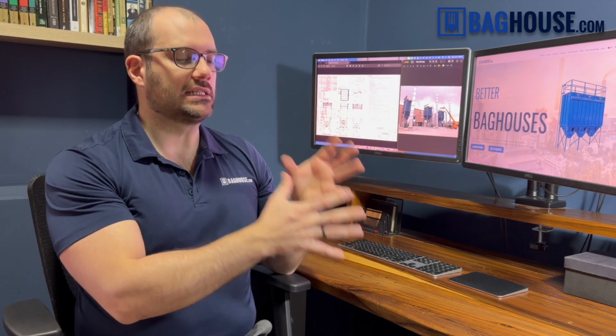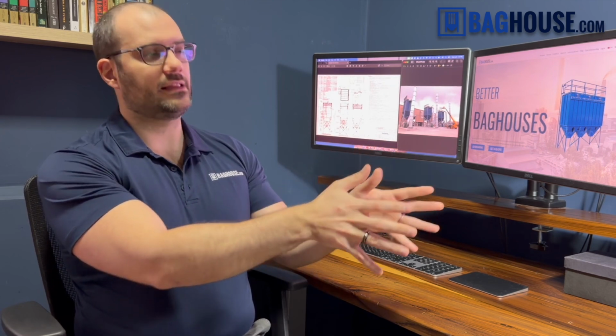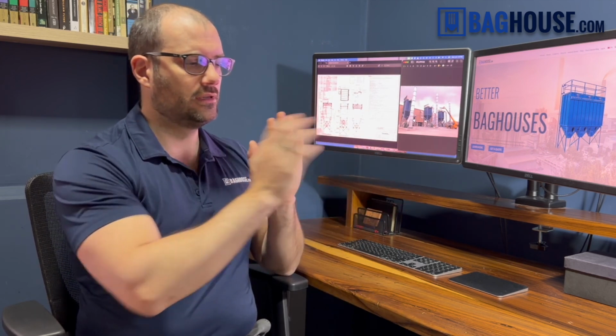One that comes to mind is a plant that had a dust collection system that was installed correctly, handling combustible dust. And they thought it was good, but they had overlooked the fact that they had pointed the explosion vents on the baghouse directly at another silo that contained combustible materials. So had anything happened, the baghouse would have been protected and worked correctly, but they would have had a vent that opened and shot a big flame ball right on another silo that had combustible dust in it. They weren't aware that that's how that would work. They thought only potentially a pressure wave would go out. So we're able to identify those kinds of problems, larger scale things.